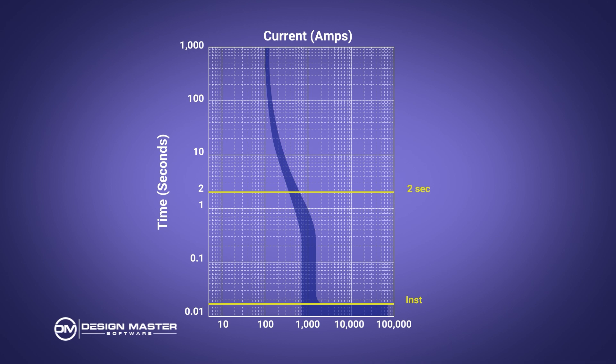When you are in that section, we'll use the appropriate trip time, but in most cases you're either going to be at a two-second trip time or an instantaneous trip time for your arc flash. To wrap up: there are three types of curves — thermal, electronic, and fuse. When using these curves, realize they're being digitized from PDFs, so don't assume more precision than actually exists. Don't substitute curves because they're all a little different. For electronic curves in particular, have some idea of how they actually work in the field when setting values. And for arc flash, it ends up being a very small range of currents where these curves actually come into play.